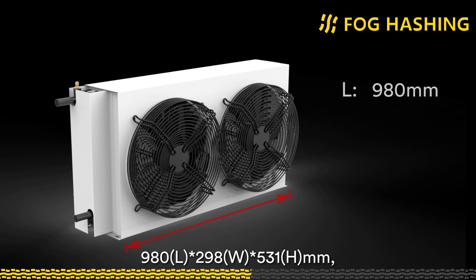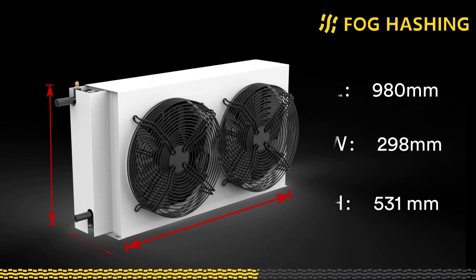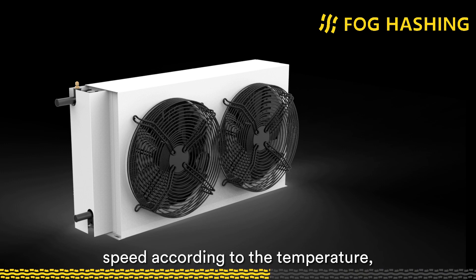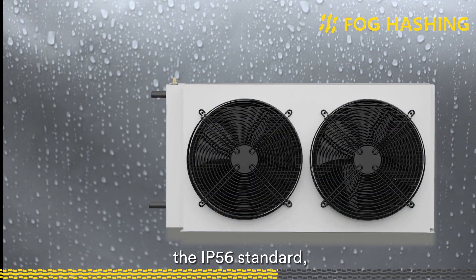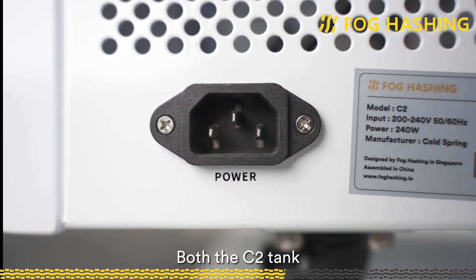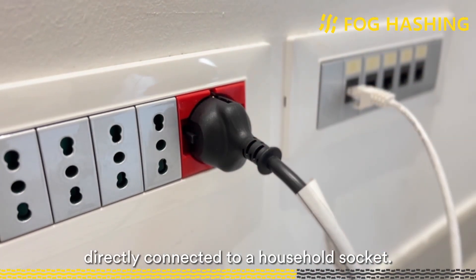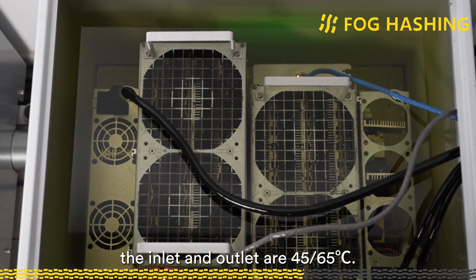The size of the dry cooler is 980 mm in length, 298 mm in width, and 531 mm in height. The net weight is 48 kg, and it also uses single-phase power at 200 to 240 V, 50 or 60 Hz. The fan can automatically adjust its speed according to temperature, with a maximum power of 440 W. The dry cooler meets the IP56 standard for outdoor use and can be exposed to rain. Both the C2 tank and dry cooler use C14 connectors, and the internal mining rig is powered separately. The coolant flow rate is 30 liters per minute, with inlet and outlet temperatures of 45 and 65 degrees Celsius.